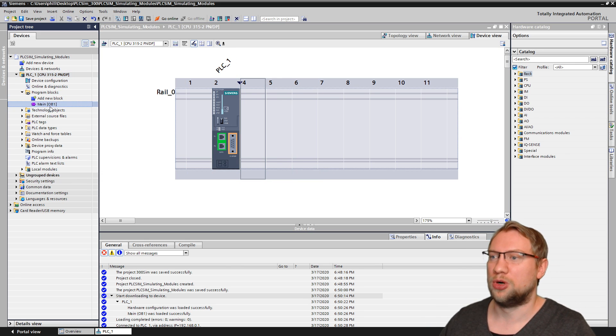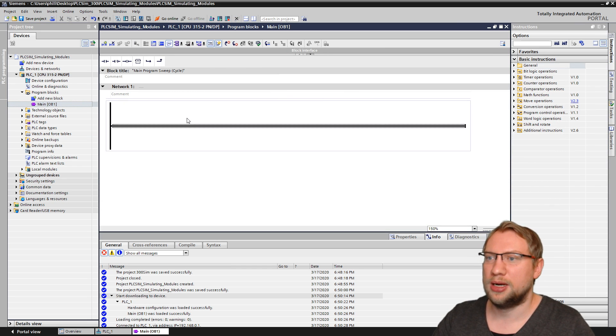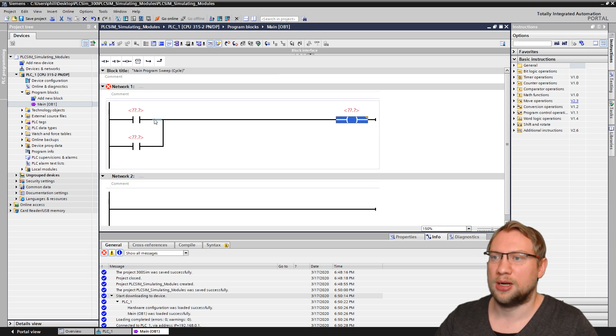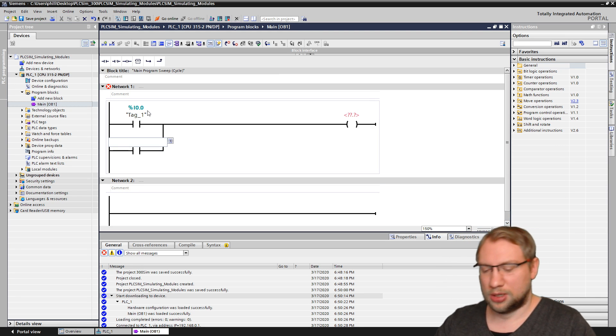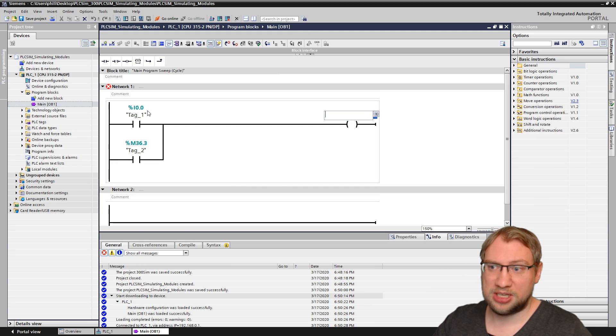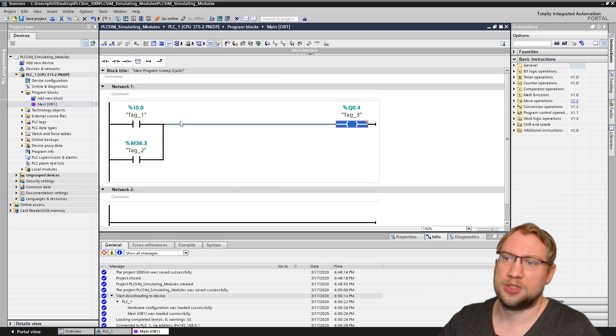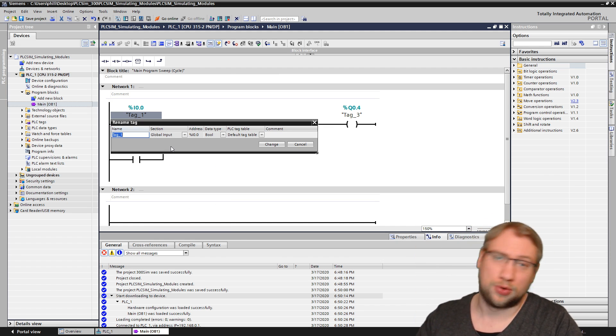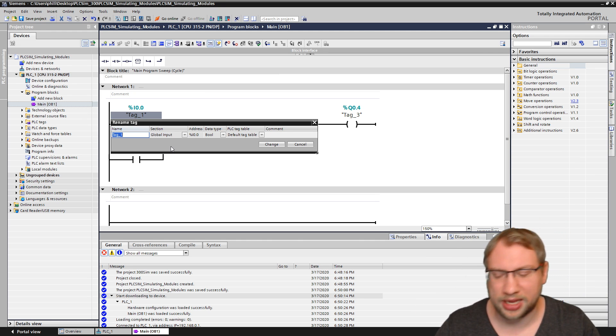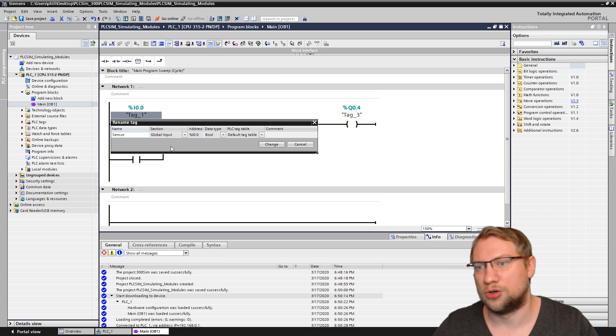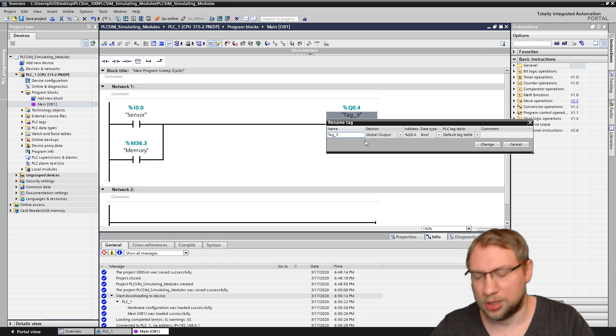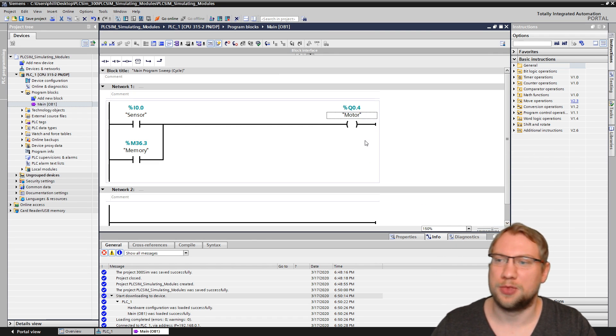Let's make a small simple program. I go to my main function and I want a very easy program. I'll create a parallel circuit with an output — I will have I0.0 and M36.3 as memory, and the output Q0.4. So it's just a very simple small program. I'll give my variables names and symbols so I can see in the simulation which one I'm controlling — not just address-based but also tag-based. This one I'll call sensor, this one memory, and this one motor.